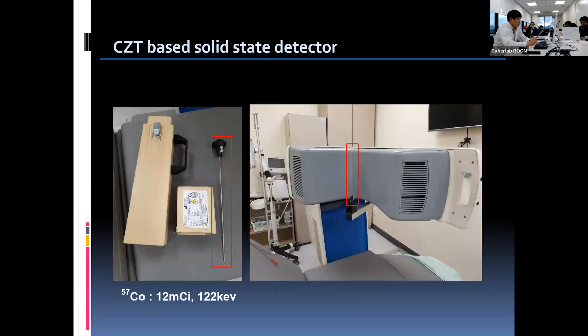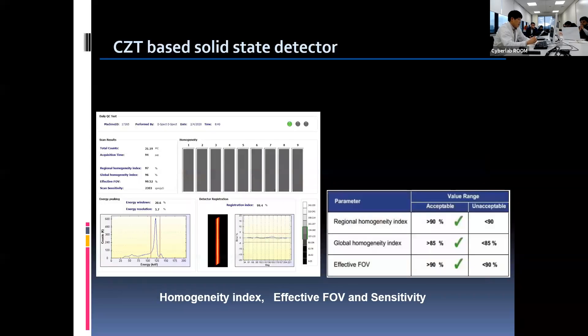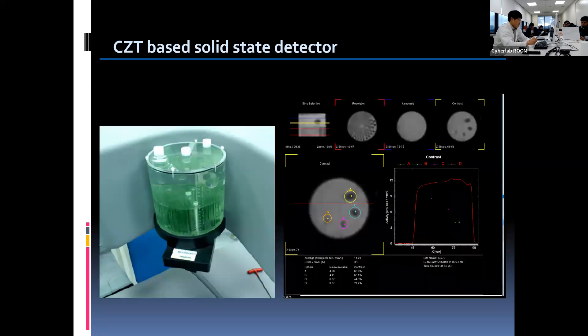For the daily QC test, a cobalt rod source is fixed onto the holder that is attached to the machine, and it is positioned vertically to cover the entire active area of the detector. Results are automatically generated once the acquisition is complete. The report shows the homogeneity index, effective sensitivity, and energy resolution. The QC process is becoming simplified and automated in modern clinical imaging systems, which is convenient for the end user. The QC process is also required to be done on this machine, and the principle of image analysis is the same as for other conventional SPECT cameras.